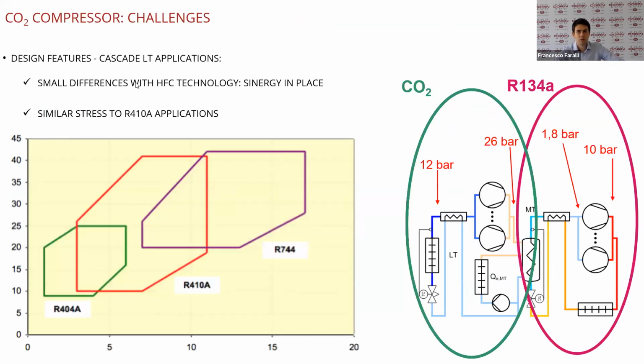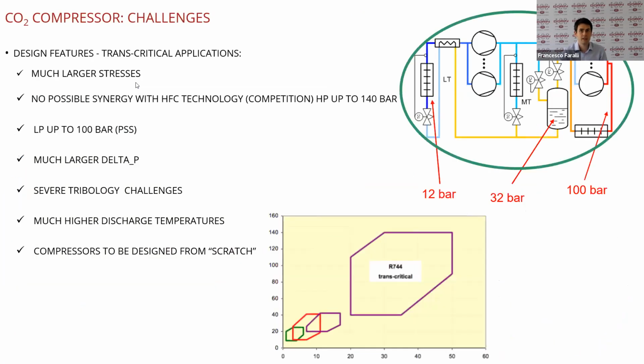So speaking of CO2, as you all know, when we speak about subcritical CO2, the pressures of the system are more or less closer to other HFC refrigerants, like for example 410A. But when we speak about transcritical systems, where the pressure of the system can go up to 110, 120 bar, obviously the working conditions of the system, and in our case of the compressor, are much more severe, because we have larger stresses on the mechanical components because of the larger delta P. And also from a lubrication point of view, obviously it's not the same as a Freon compressor.